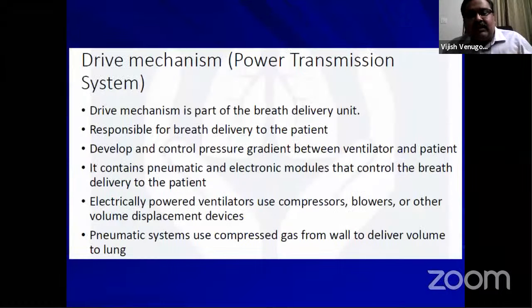Now, what is the drive mechanism? The drive mechanism is part of the breath delivery unit. They develop and control the pressure gradient between the ventilator and the patient. So there are two elements. It has both pneumatic and electronic modules.